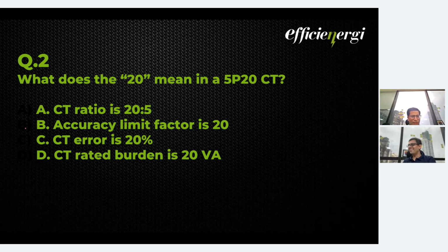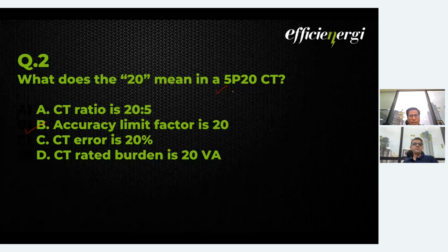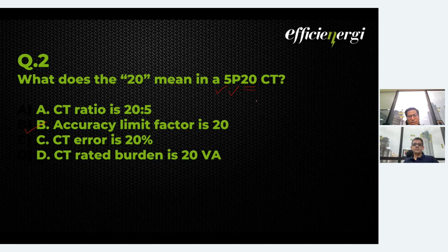Actually, this is the accuracy limit factor. So the first is your percentage accuracy. P stands for a protection current transformer, and the 20 stands for accuracy limit factor 20. So that means up to 20 times the rated primary current, or the secondary current, the accuracy limit will be plus minus 5%. So this is basically the meaning of this 5P20 CT. So in protection, we normally get 5P20, 5P10.